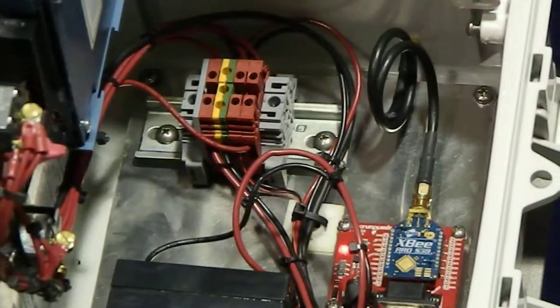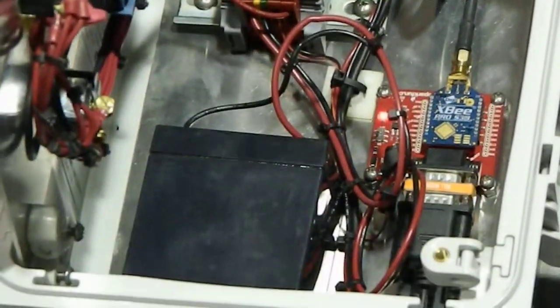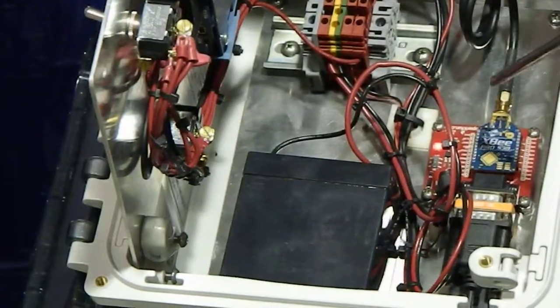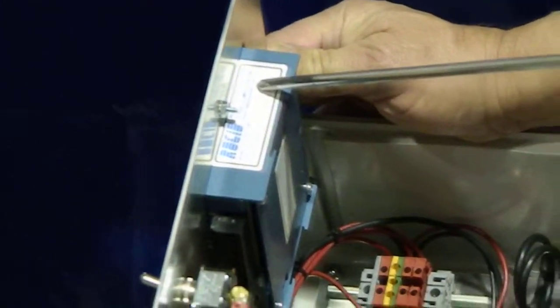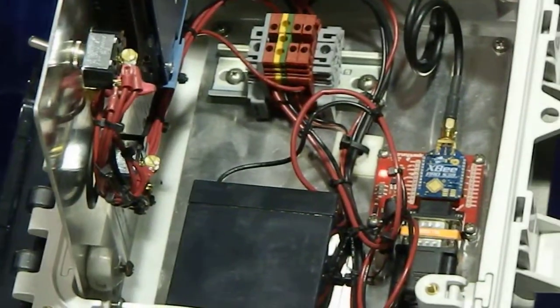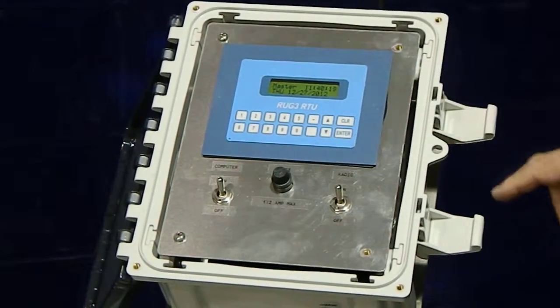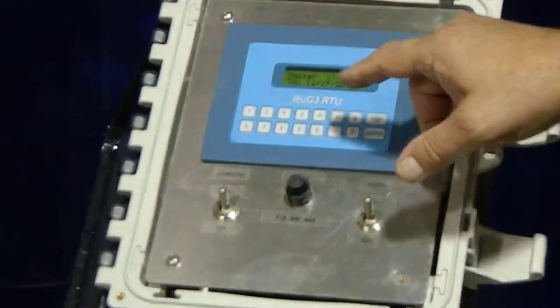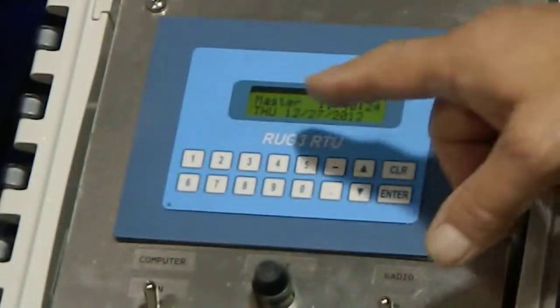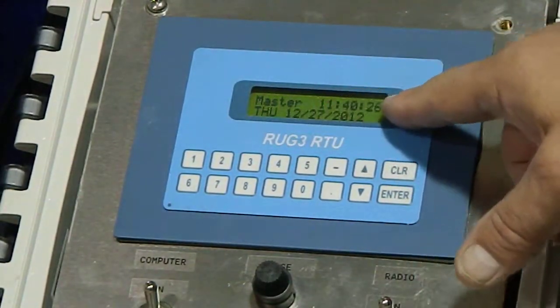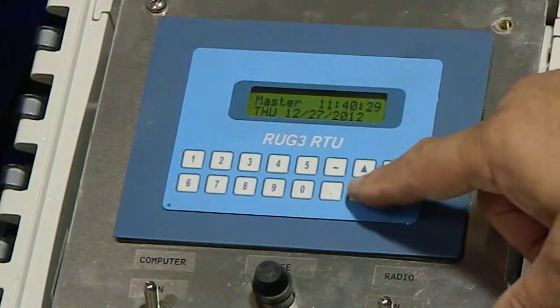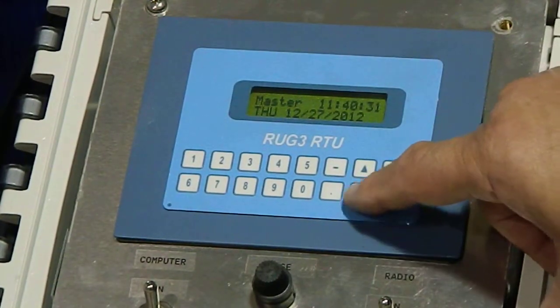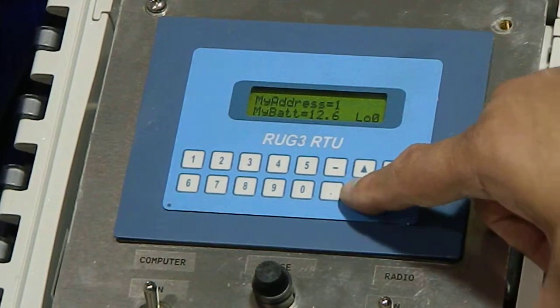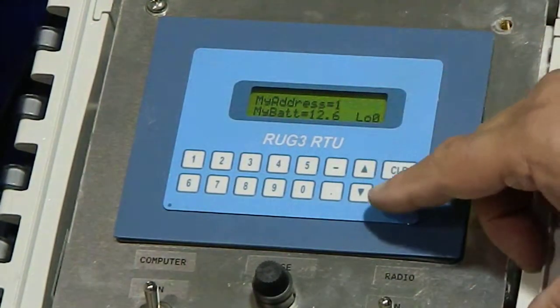Inside the unit, you can see a small battery, a radio, terminal strip, the backside of the controller, and our switchgear. Very easy access. Now we're going to go through the screens. Each screen on all of our systems indicates what it is, the time and date of the system. We move the screen to the next one by going the up or down arrows. This says this address, the battery voltage.